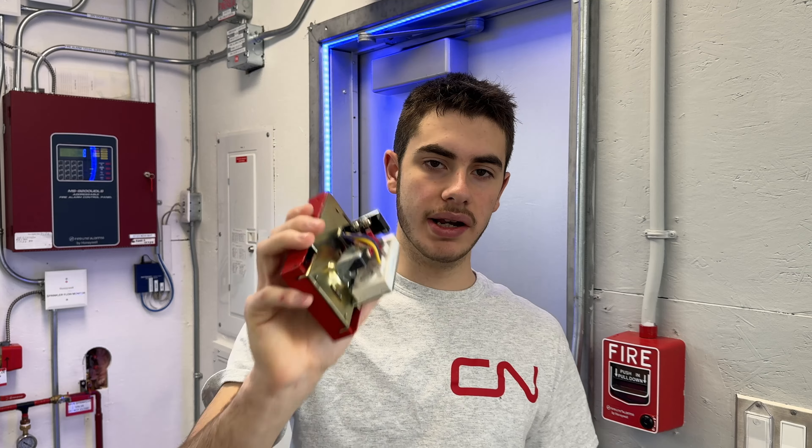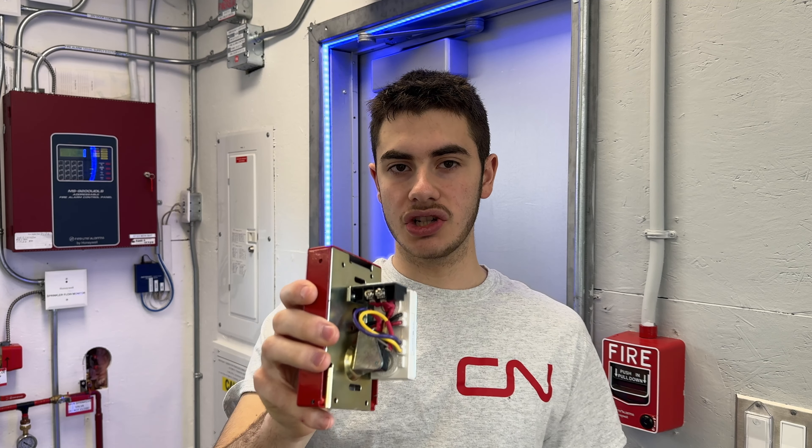There are two possibilities here for what we might do with this. One is replace the monitor module if that's the issue, which it likely is, or we just turn this into a conventional pull station. Now obviously in the field you're not allowed to do that — you're not allowed to repair your own devices; they have to be from the manufacturer. As soon as you repair it or touch anything it loses its UL and CSA listing and is no longer legal. That's why when you get a defective product like this the option is to send it back to Honeywell for replacement or throw it out — often it's more efficient to just throw it out.